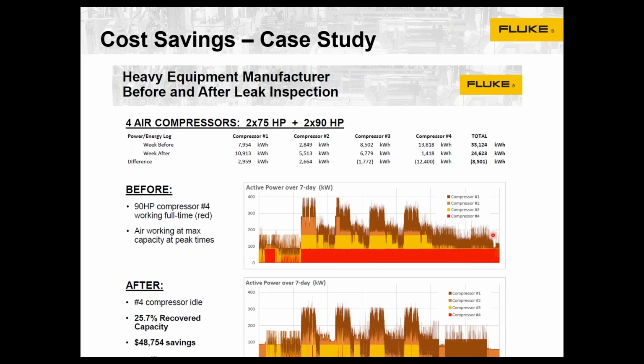So the actual numbers show that, over the course of a week, they were using about 33,000 kilowatt hours, and they were able to reduce that to under 25,000. So around 8,500 kilowatt hours saved just by fixing leaks. If you annualize that, they show that they recovered over 25% capacity, that 4th compressor is sitting idle now, and that represents about a 48 plus K savings. So big benefits.